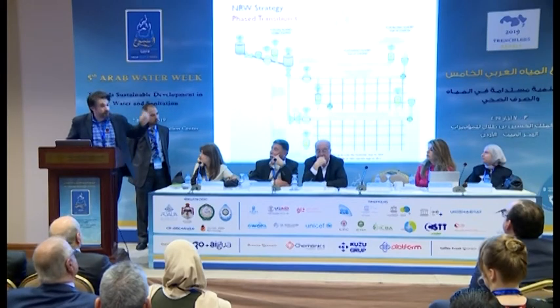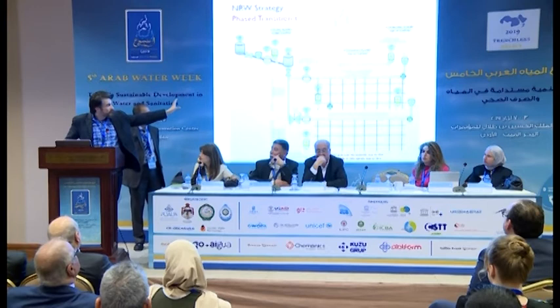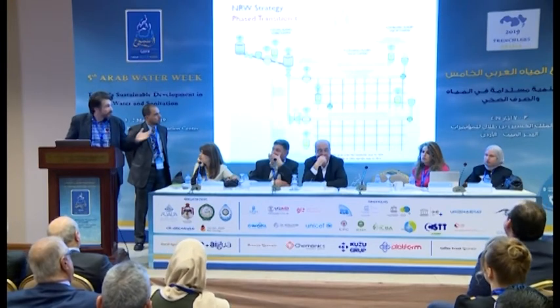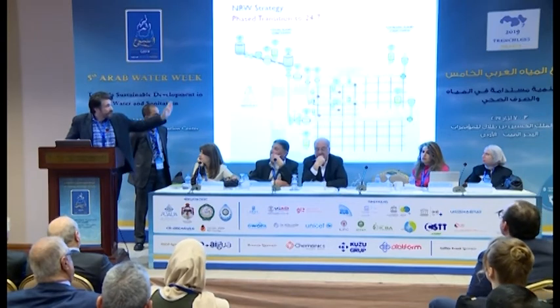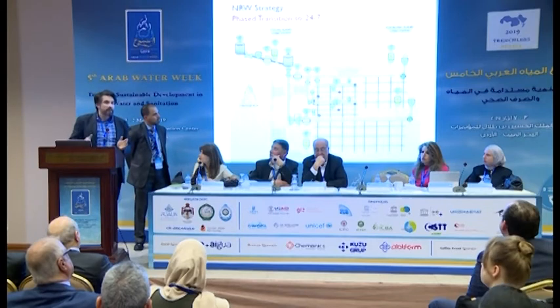Next step, we go to the DMAs. One by one, we take the distribution zone and install pressure monitoring. We fix the network hydraulics. Many of these networks are not hydraulically optimized. They are random networks. And then we go to the DMAs. One by one, we convert them to 24/7.